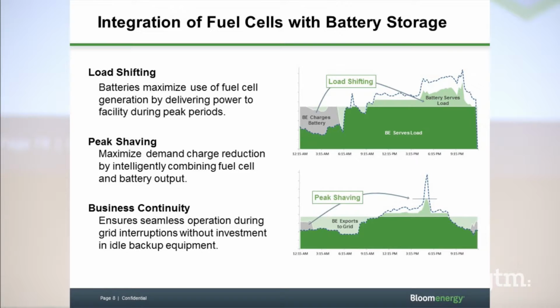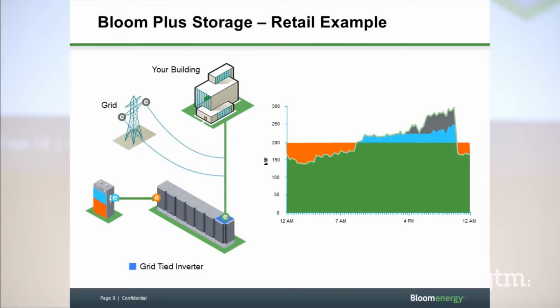If you look at the load curve of a retail customer, essentially what we're doing is during the nighttime hours we are charging the battery. Once the battery is charged, because there's very little load in the store, we can then discharge the battery coinciding with peak energy charges, essentially eliminating almost all of their peak energy charges for the store. We also have enough capacity in the battery to go after the demand charge peak at the specific time. We take all the 15-minute data, crunch it, and use an intelligent algorithm to decide how the battery is dispatched.